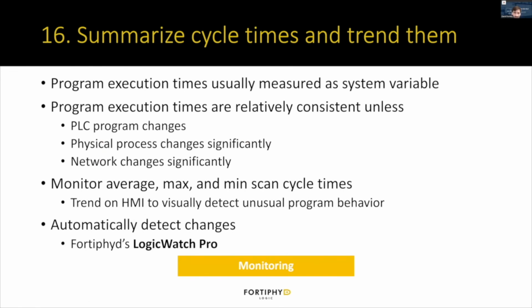Number 16 is summarizing cycle times and trending them on the HMI. Program execution times are usually available as a system variable in the PLC, and these times are relatively consistent. It's executing the same program over and over again, with not many changes unless the program itself changes, or the physical process significantly changes and executes new branches of code that it never did before. Or if there are significant changes in the network, it might cause some timing issues in the PLC program. The idea here is monitoring the average, max, and min scan cycle times, trending them on the HMI to visually detect changes, and maybe setting some alarms to detect obviously bad cycle times.